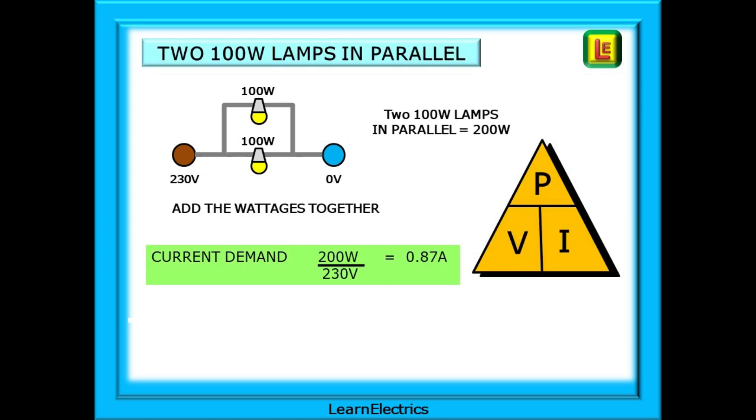With two 100 watt lamps in parallel we have 200 watts of lighting energy, so how much current is that? With a parallel circuit two lamps will draw more current than a single lamp, so 200 watts divided by 230 volts is 0.87 amps: twice the current, twice the amount of light.